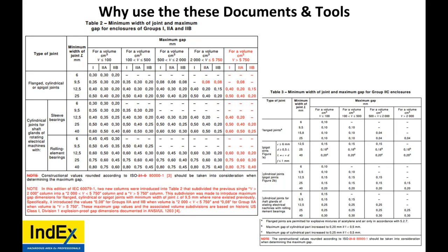Too many questions. When a U certificate is supplied to a manufacturer, does the manufacturer need to certify after the assembly is over? Yes. Well, if they plan on creating a product, let's say you get an empty enclosure and then you add a PLC inside of it. Now they have a new product. They then have to send it to an ExTL and CB, testing laboratory and certification body.